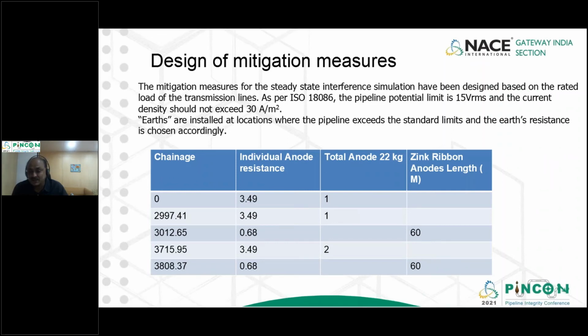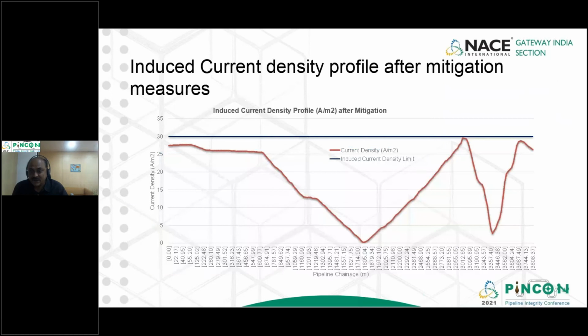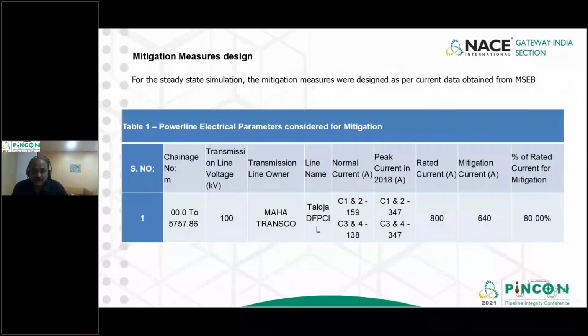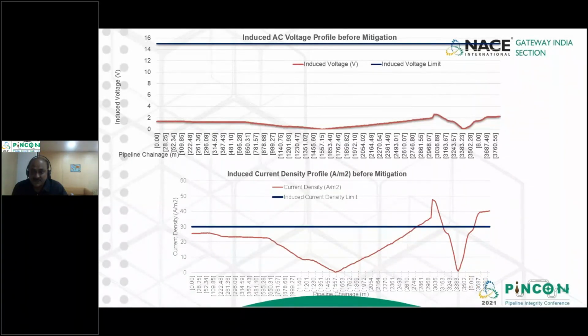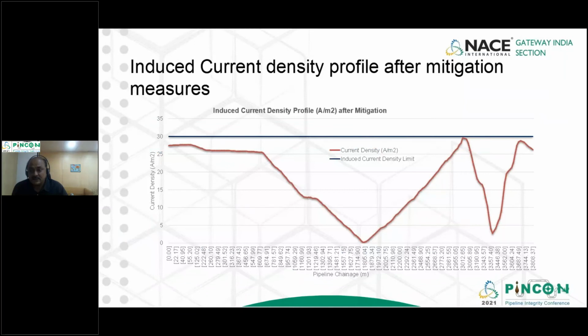And then zinc ribbon, we have installed 60 meters at 3012 chainage and 60 meters at 3808 chainage. These are the places where, if you go back, you will find that we were having issues. Once we did this, you see the current density after these mitigation measures were done. We are well below 30 amps per meter square. So we then gave clearance for putting gas into the pipeline, because many big customers were there, and we were not able to commission them because of this AC current mitigation issue. Once we found things were okay, we gave permission to commission the pipeline.